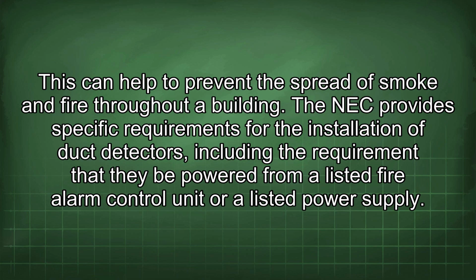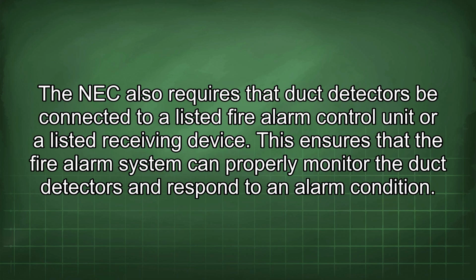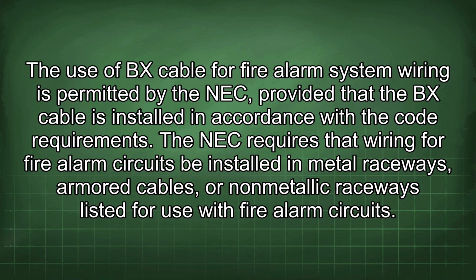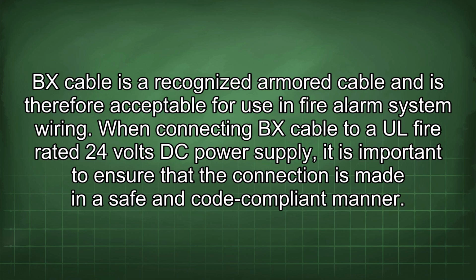The NEC provides specific requirements for the installation of duct detectors, including the requirement that they be powered from a listed fire alarm control unit or a listed power supply. The NEC also requires that duct detectors be connected to a listed fire alarm control unit or a listed receiving device. This ensures that the fire alarm system can properly monitor the duct detectors and respond to an alarm condition. The use of BX cable for fire alarm system wiring is permitted by the NEC, provided that the BX cable is installed in accordance with the code requirements. The NEC requires that wiring for fire alarm circuits be installed in metal raceways, armored cables, or non-metallic raceways listed for use with fire alarm circuits. BX cable is a recognized armored cable and is therefore acceptable for use in fire alarm system wiring. When connecting BX cable to a UL fire rated 24 volts DC power supply, it is important to ensure that the connection is made in a safe and code compliant manner.